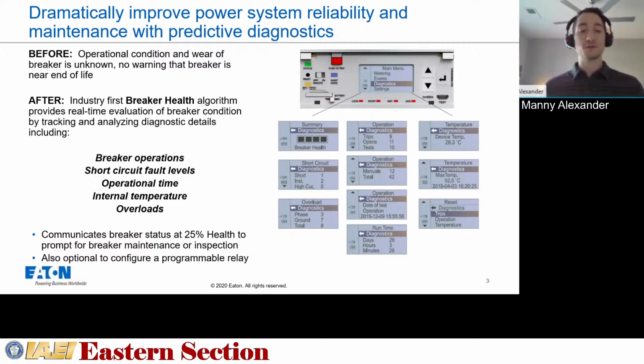So with the advanced features of the Power Defense breakers and the PXR electronic trip units, Eaton has introduced this powerful diagnostic capability into our molded case breakers and insulated case breakers. So the PXR is smart enough to monitor variables such as how many faults has the breaker seen and how high were those faults. Has the breaker encountered an overload condition? How many times has the breaker been physically operated? Is it used as an on-off switch or left alone in the field? Maybe how long has the breaker been in service in terms of days and hours and even minutes? What's the internal temperature of that breaker? Is it somewhere hot and humid, or is it somewhere where it gets cold?